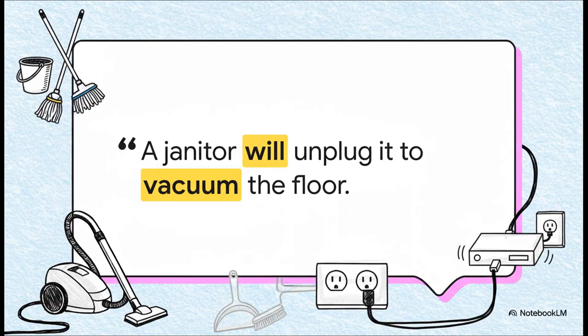And finally, I have to share my favorite piece of real-world, hard-won wisdom. It's a rule known as the janitor's outlet. Never, ever, ever plug your main security server or your video recorder into a standard, unprotected wall outlet in a closet or a hallway. And the reason is simple: because sooner or later, a janitor will unplug it to vacuum the floor. I know it sounds funny, but it is a catastrophic and shockingly common point of failure. You have to hardwire it or use a special locking plug.